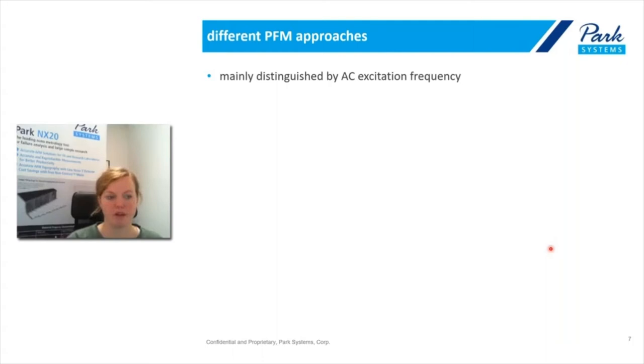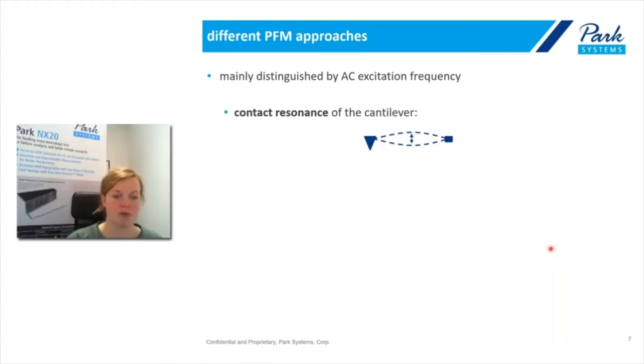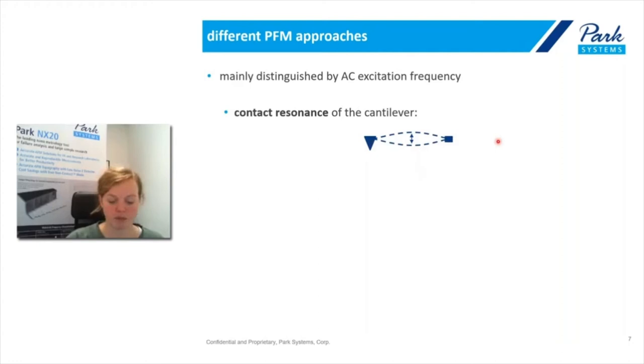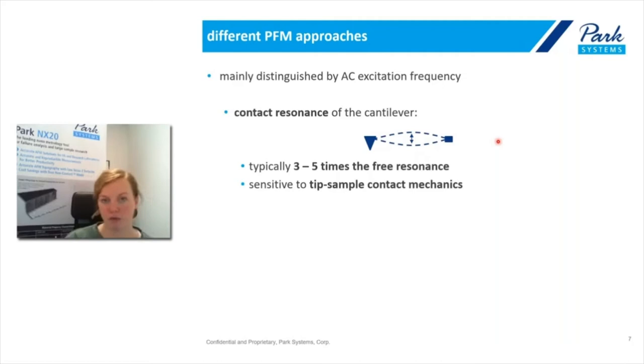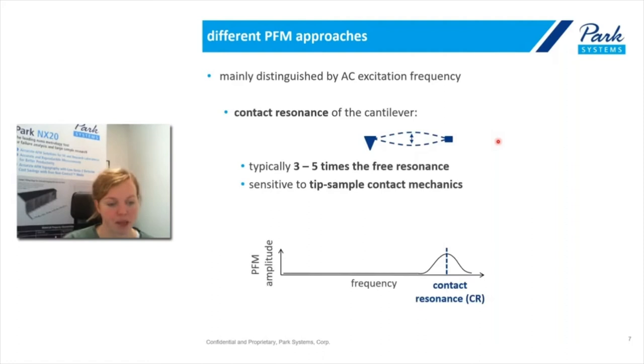There are different approaches to perform PFM, and the main distinguishing factor is the frequency chosen for the AC excitation. One important value here is the contact resonance of the cantilever. In contact resonance, we look at a standing wave motion of the cantilever because both sides are fixed — one to the chip and the other because the tip is in contact with the sample. The contact resonance is typically three to five times higher than the free resonance, and it is very sensitive to tip-sample contact mechanics, as I will show on the next slide.